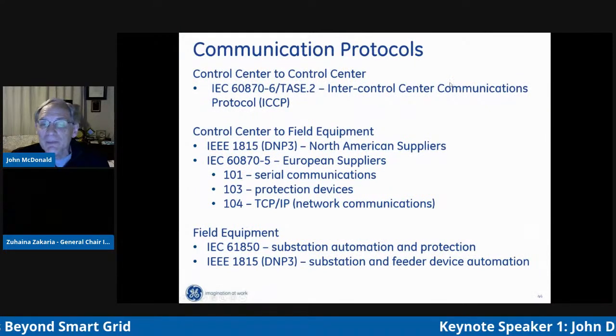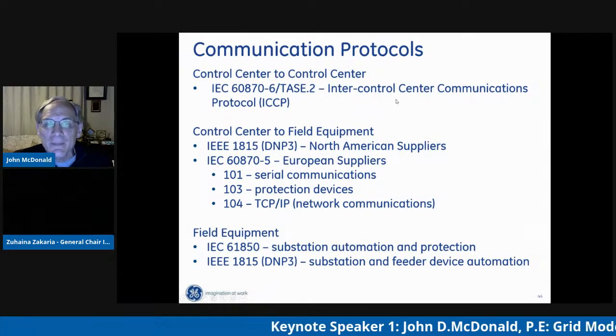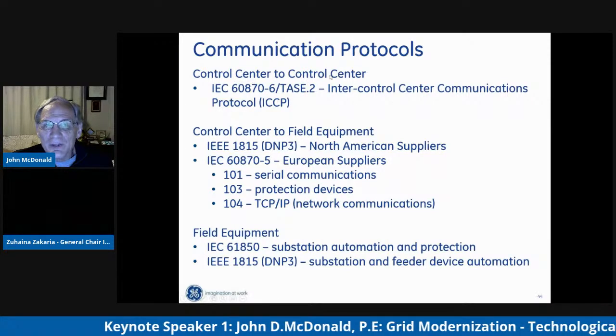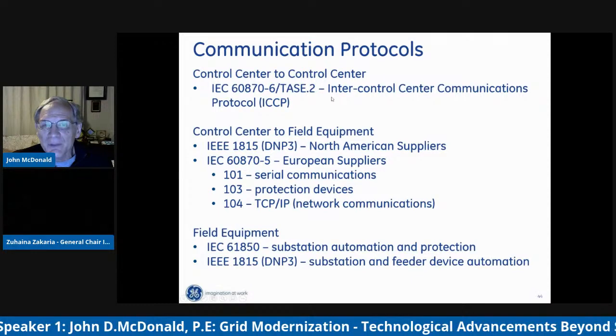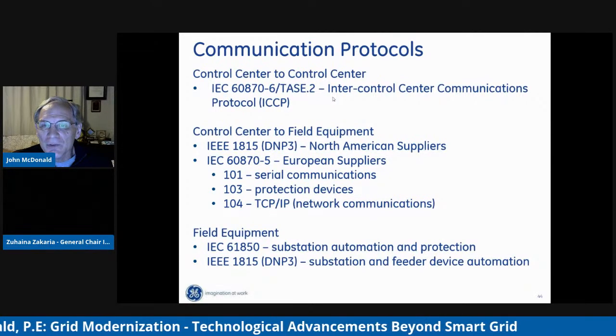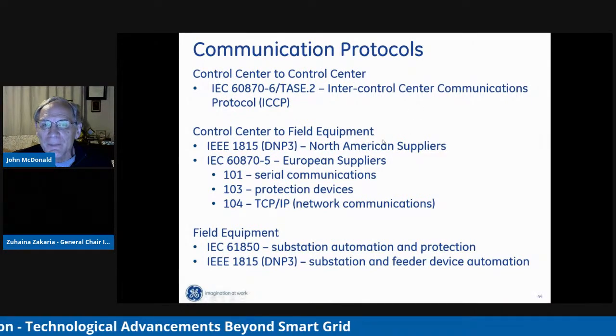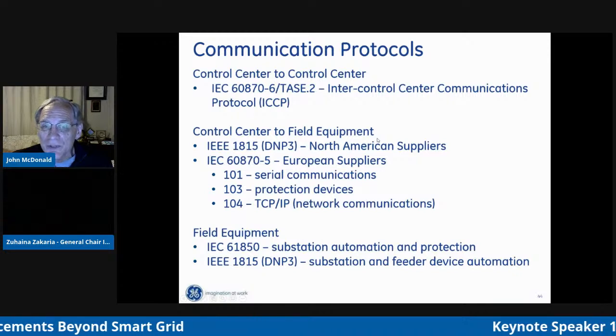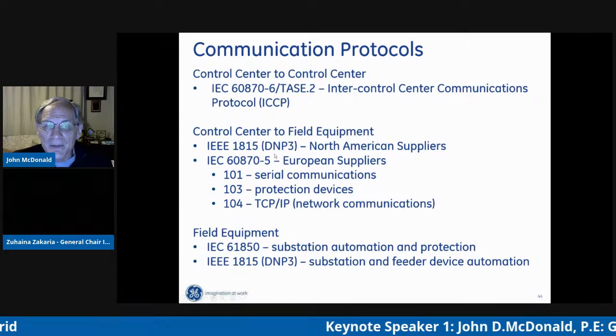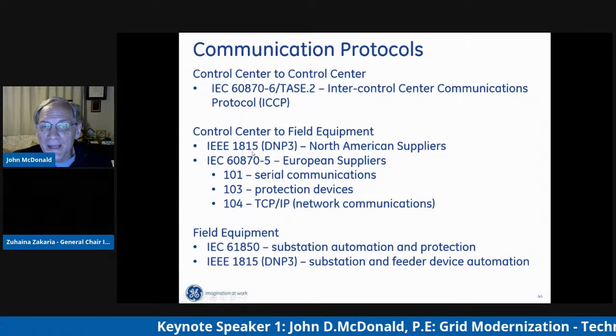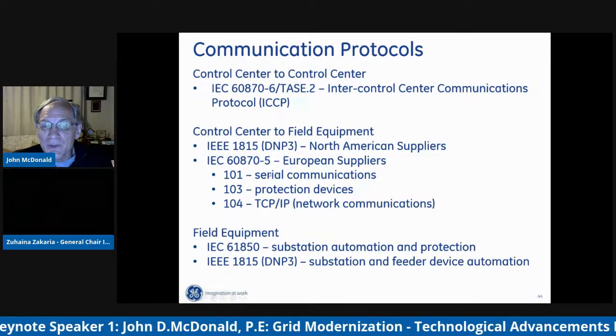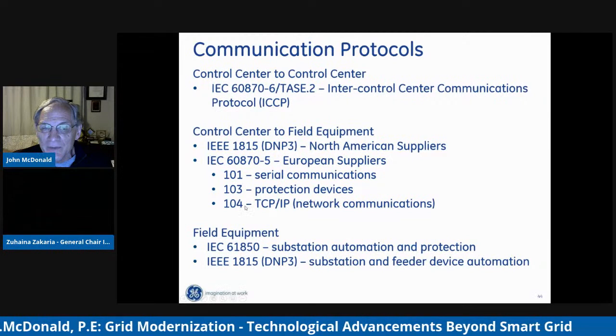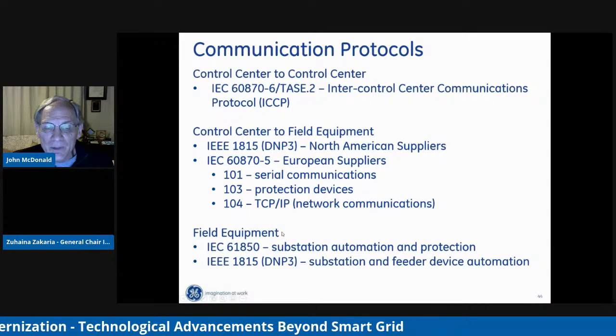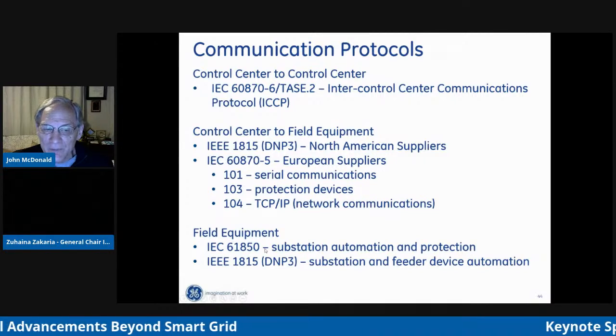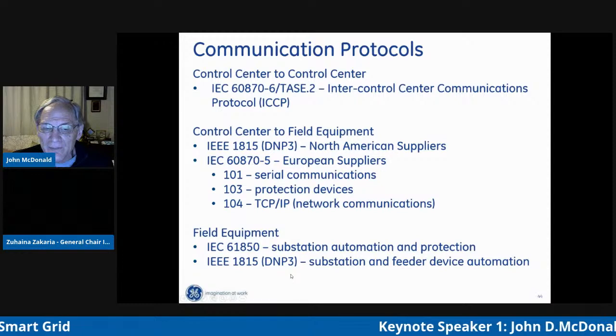Having led standards work worldwide for 35 years: from control center to control center, there's one standard accepted worldwide, Inter-Control Center Communications Protocol, ICCP. From control center to field, there are really just 2 standards: North American suppliers use DNP3, which is IEEE standard 1815, while European suppliers use 870-5 for serial communications and 104 for network. Within the field, the worldwide standard is IEC 61850, but in North America we still use a lot of DNP3 in the substation and for feeder device automation.